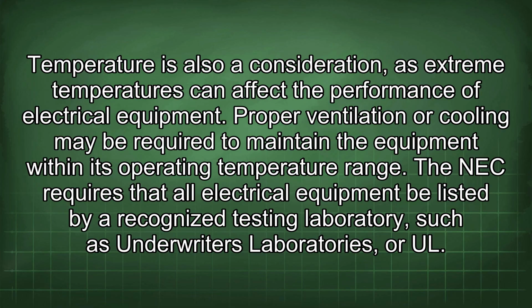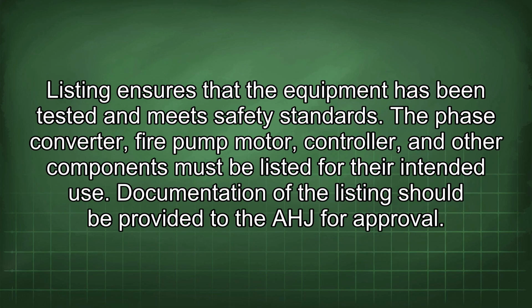The NEC requires that all electrical equipment be listed by a recognized testing laboratory, such as Underwriters Laboratories, or UL. Listing ensures that the equipment has been tested and meets safety standards. The phase converter, fire pump motor, controller, and other components must be listed for their intended use. Documentation of the listing should be provided to the AHJ for approval.